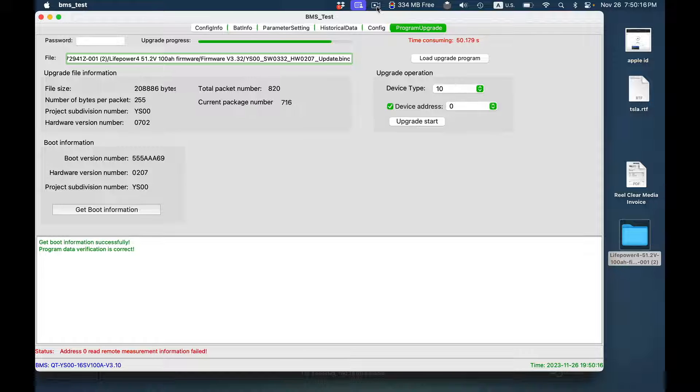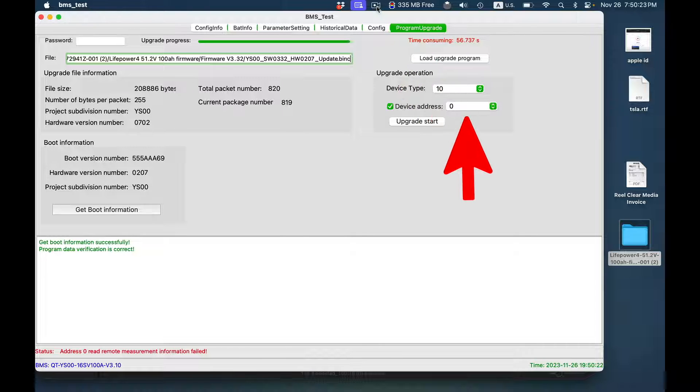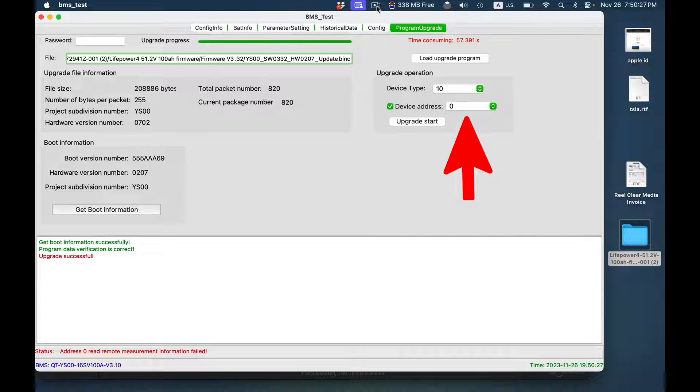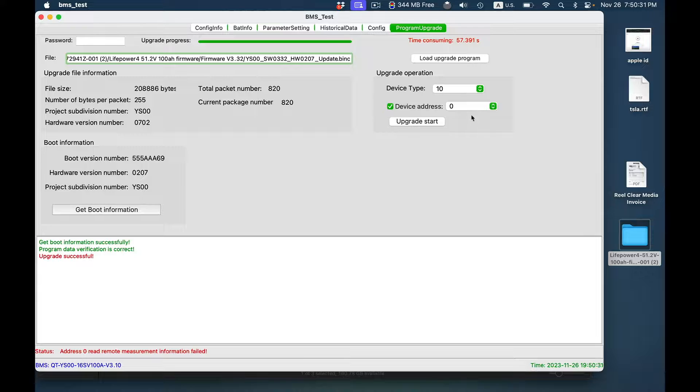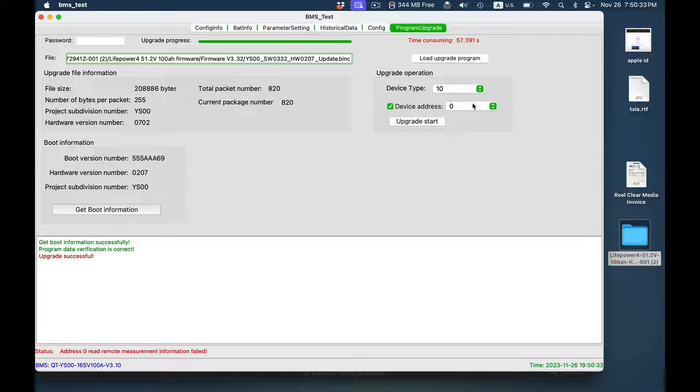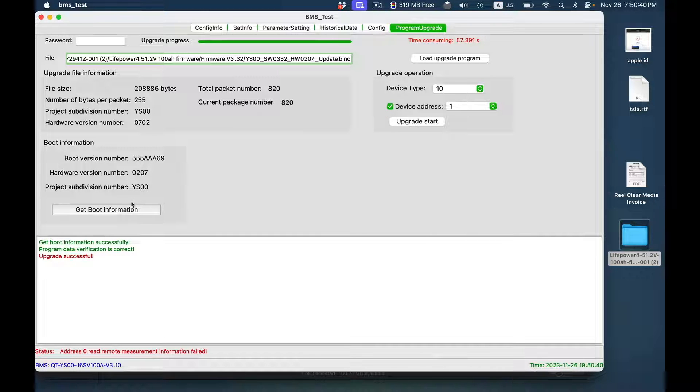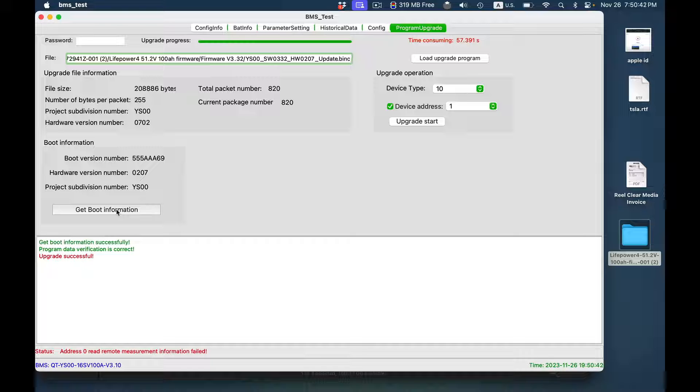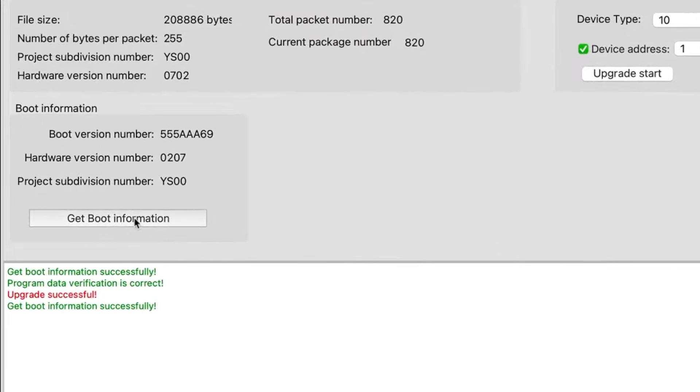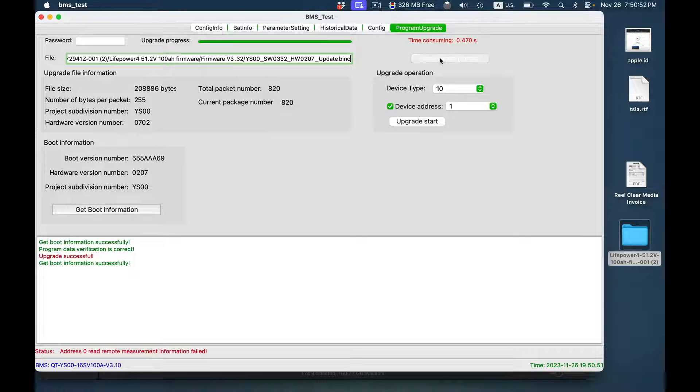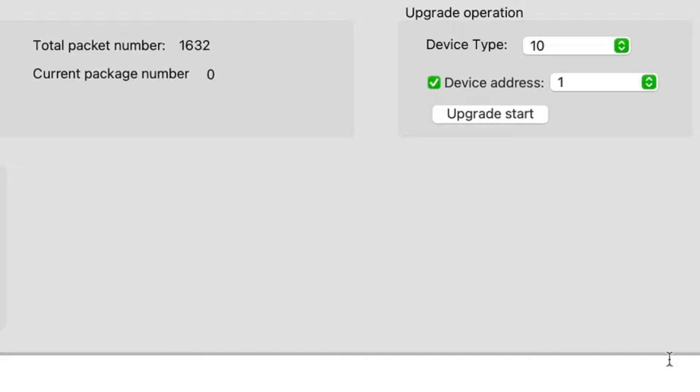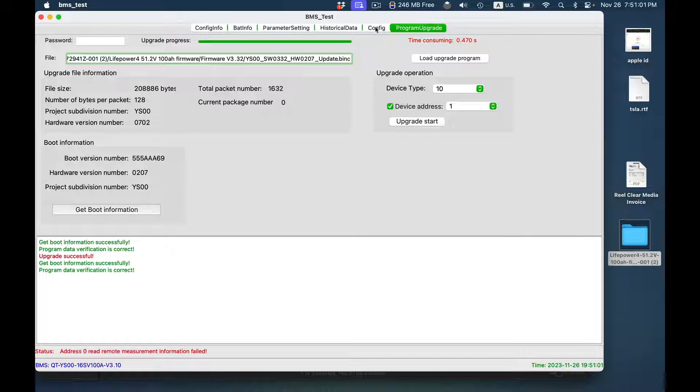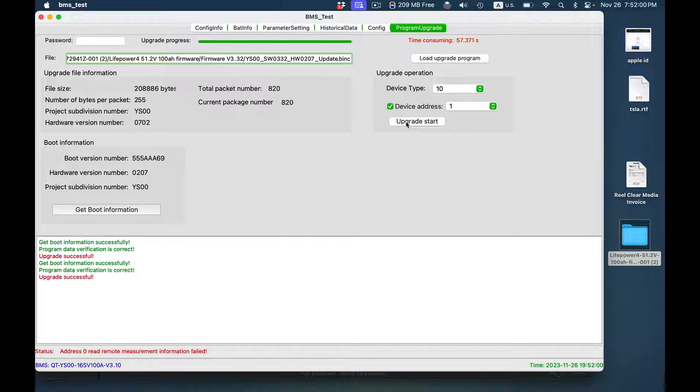I also have some pretty good videos on how to do this. But I'm under the last tab, and right now I'm upgrading my first battery. So the device address over here is zero, and that's the same as the dip switches on the front of the battery. So we just finished that. So I'm going to work on my second battery, and its address is one. And then, what you have to do is get boot information. And you're looking for this hardware version number right here, 0207 in this case, because when you load the program, there's two choices there, and you want to make sure you get the right one, the one that has 0207 in it. So there we go. We open that, and simply just hit upgrade start. I'm going to fast forward through this. So the upgrade is successful, and both of the batteries have new firmware in them.